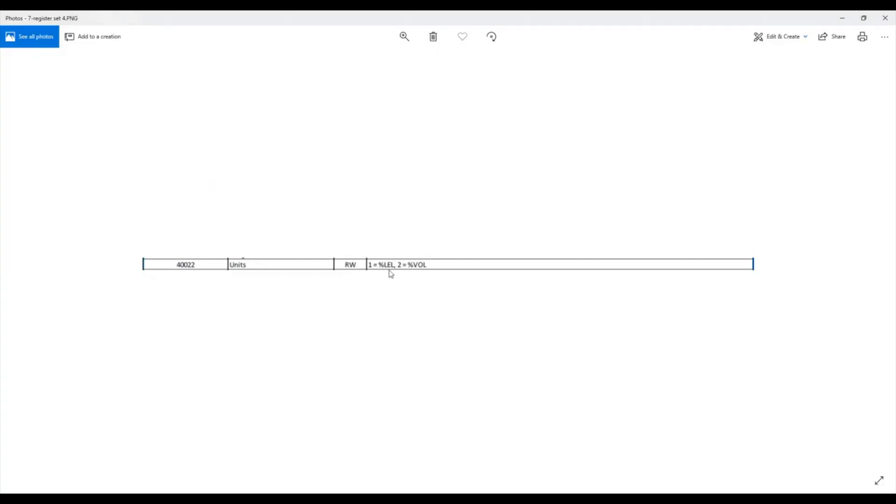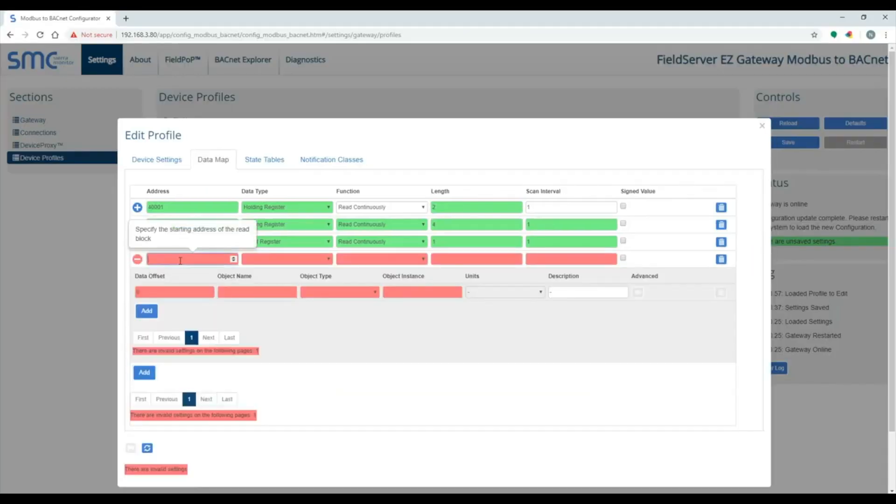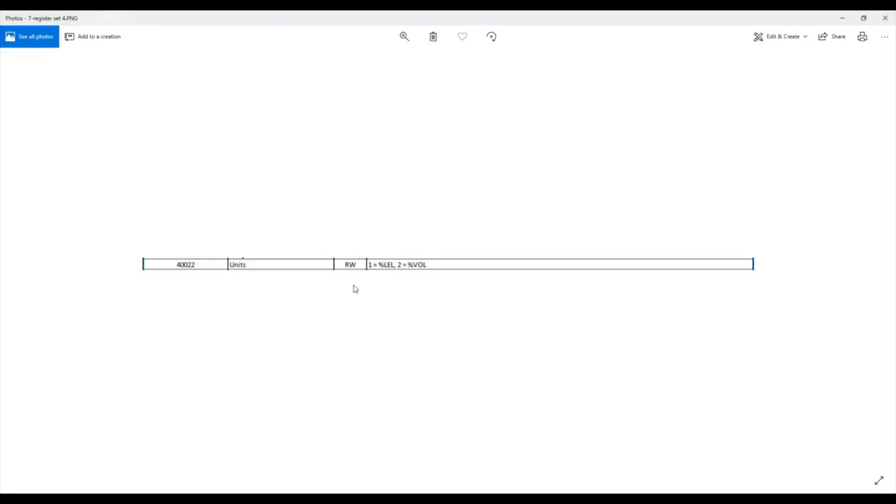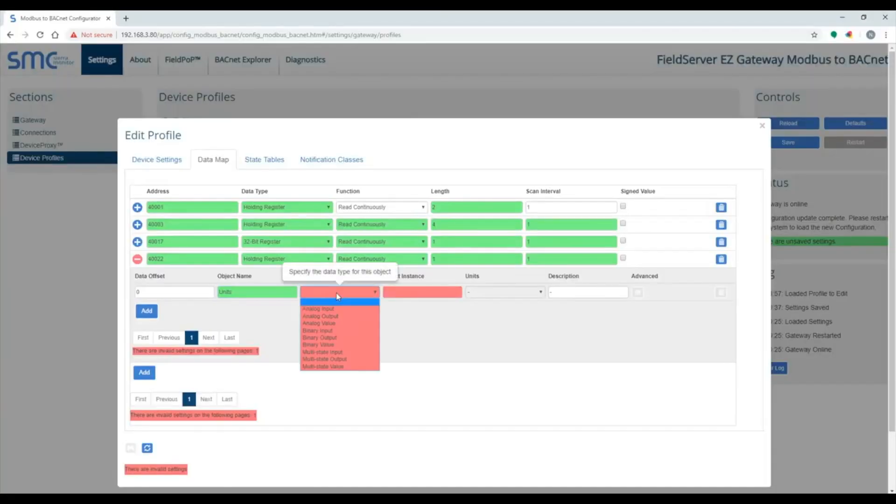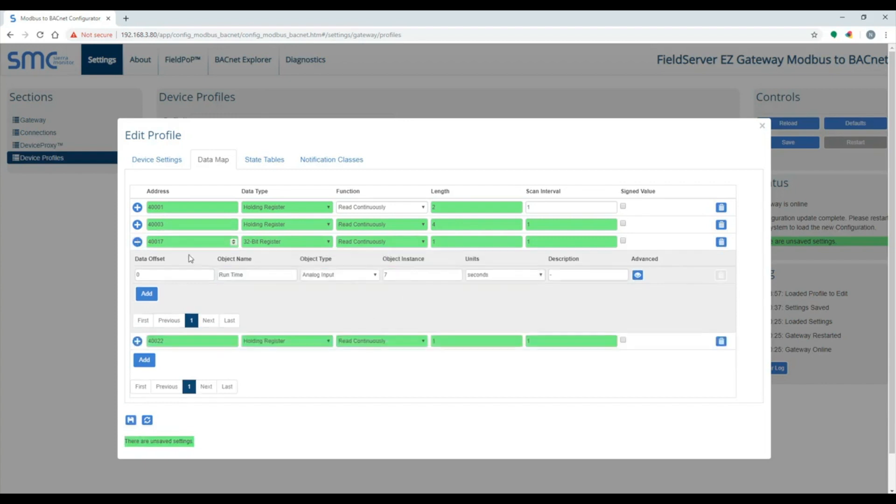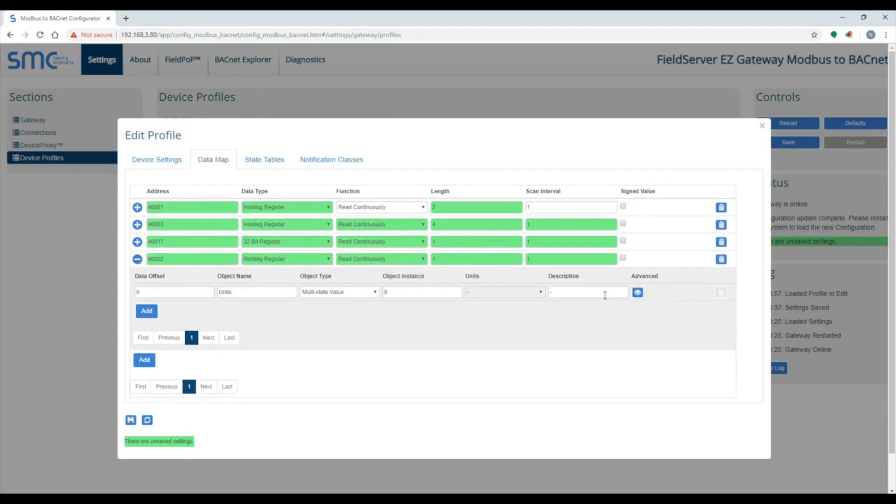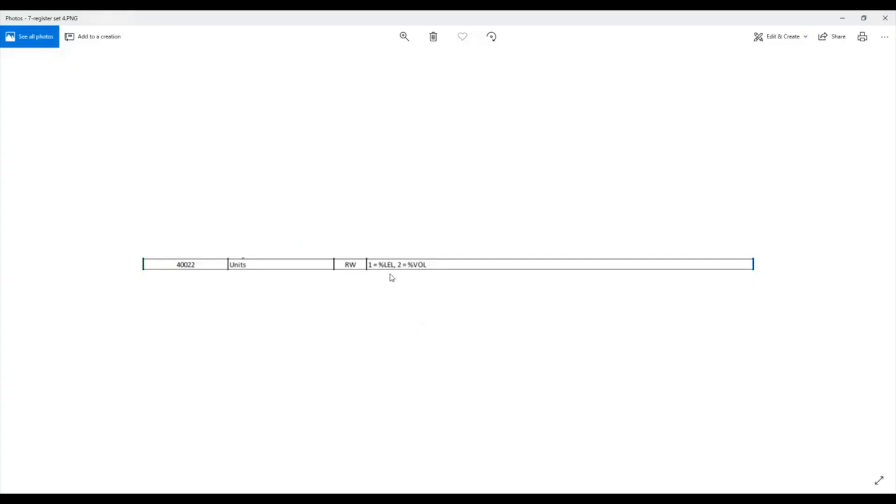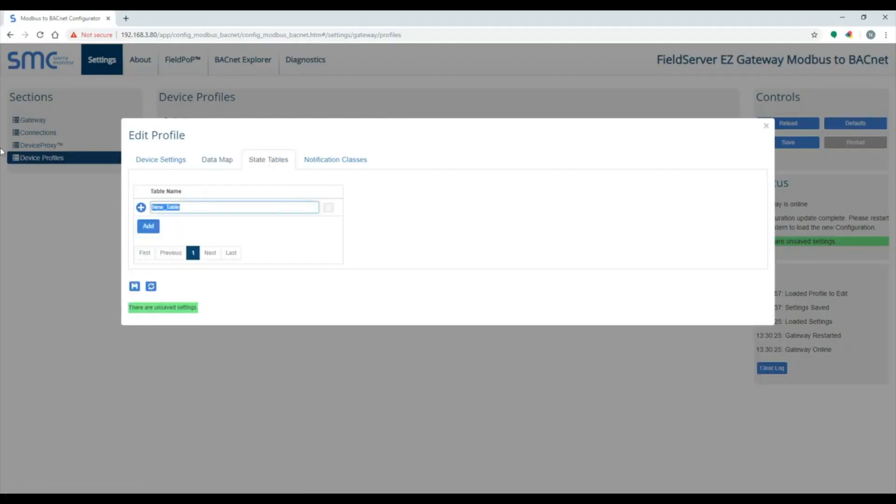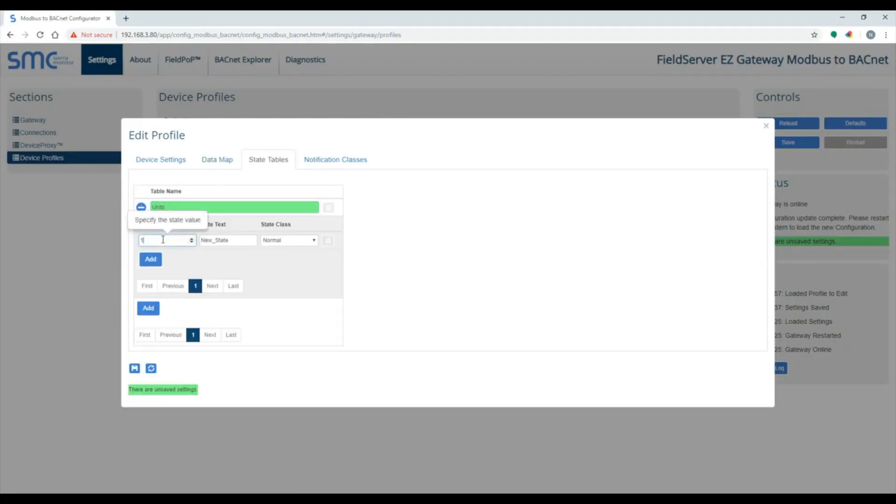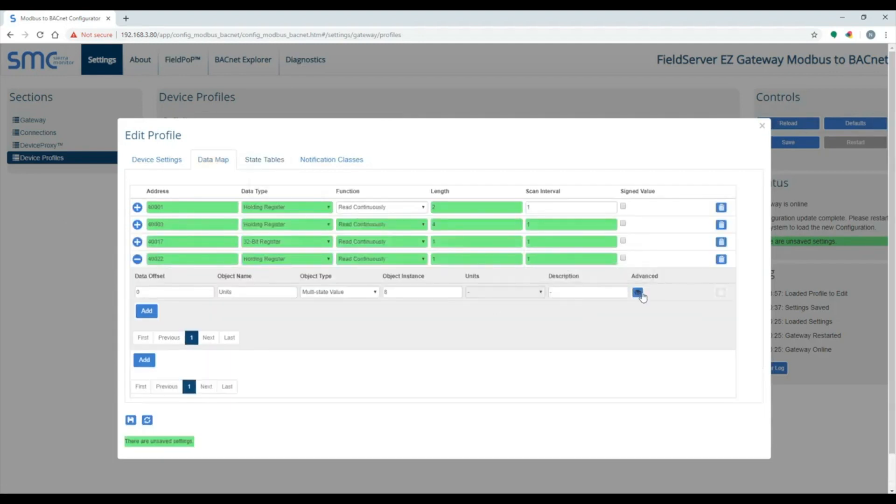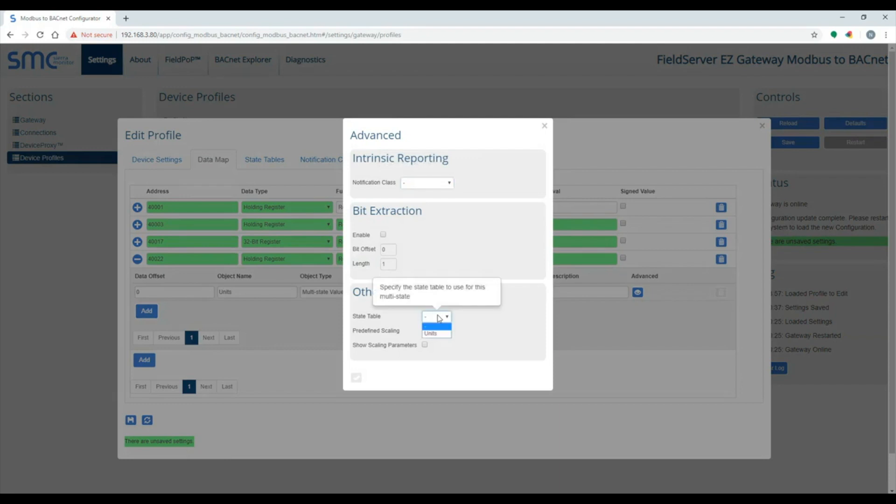The next point has state text. You need to use object type multi-state value. Then you need to define a state table. A value of 1 equals %LEL and a value of 2 equals %VOL. After the state table is created, specify that state table in the advanced section.